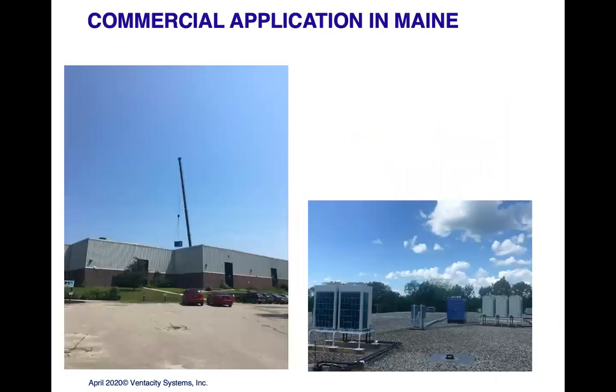Just to give you a little insight, this is a project we actually did in Maine, so again, I'm going to give you a scope of how you can apply this model. This is a commercial facility, about 30,000 square feet, that we were doing a retrofit on. You can see a crane lifting a 3,000 CFM ERV into place. Then you'll see on the roof, the heat pumps and the ERV are positioned. And that's what it looks like inside.